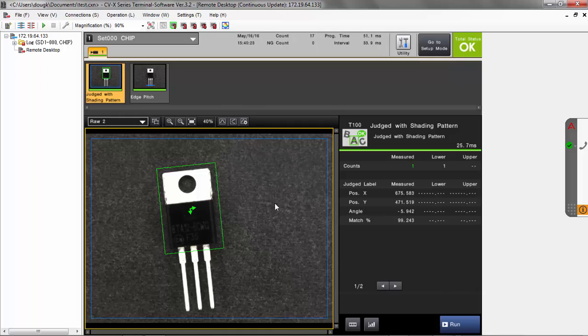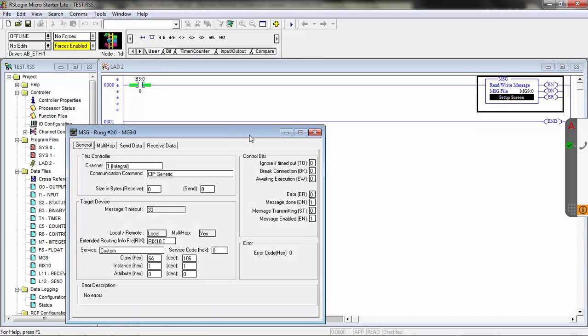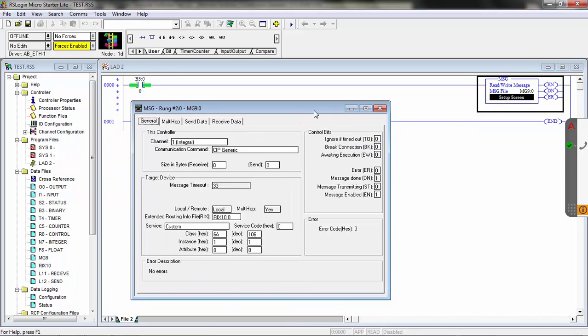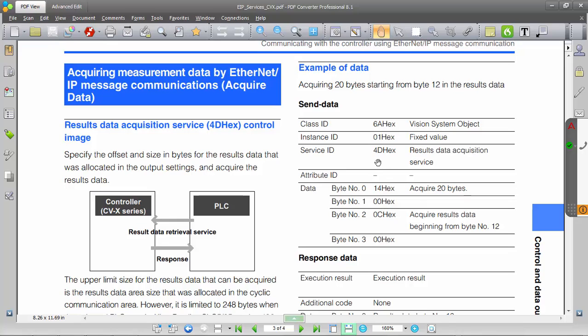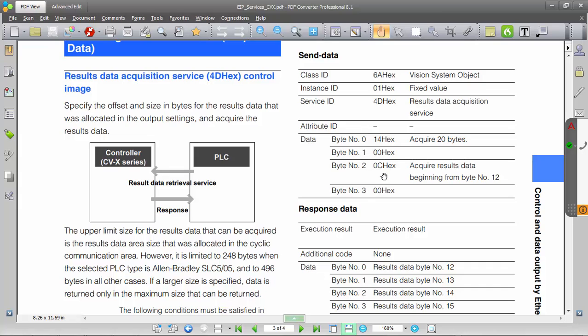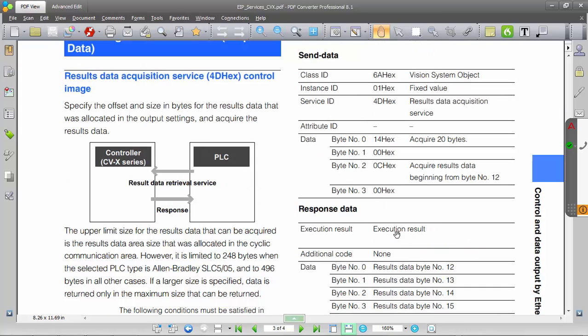Next we'll show you how to set up the message on the PLC. We have the PLC connected — this is a MicroLogix 1100 PLC. We have a basic message already started up here. I'll click on the setup screen for the message to show you how this is set up. We're going to show you the data acquisition service, which is service code 4D. If I pull up the manual, you can see it's 4D as the service ID.